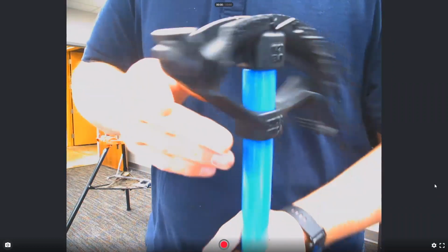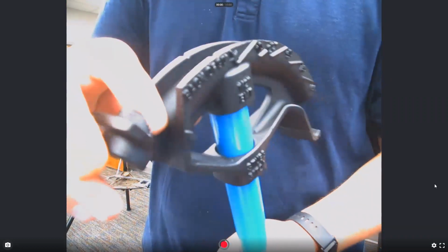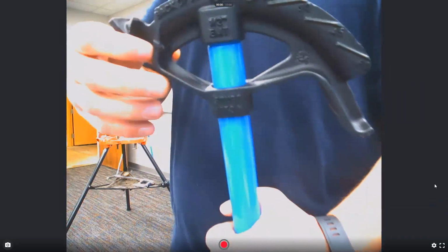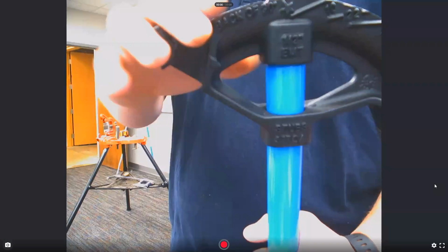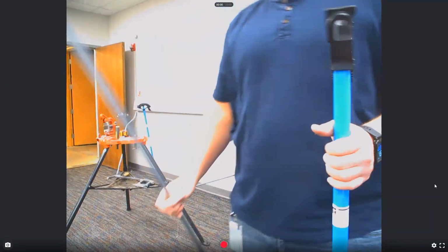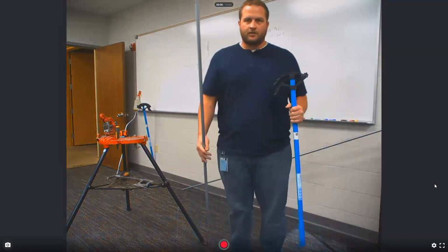If you look inside the shoe, you can kind of see that the arrow lines up with where the start of the bend actually starts to happen. So when I put that mark on the arrow and then bend it up 90 degrees, it's going to end up hopefully right at 9 3/8 inches.